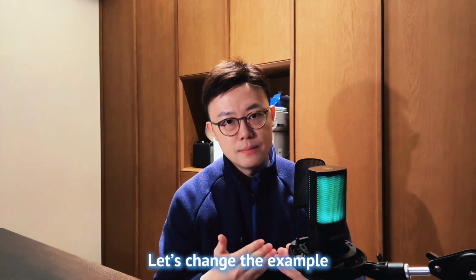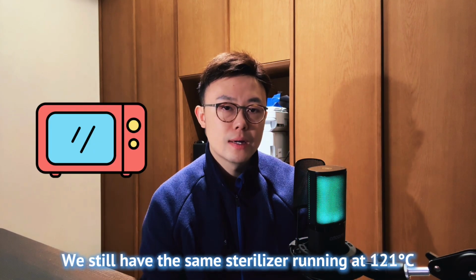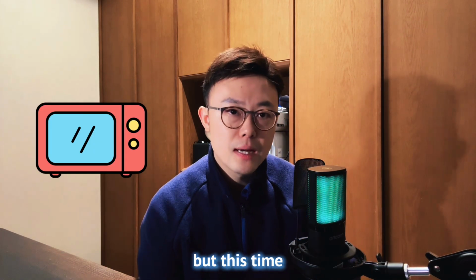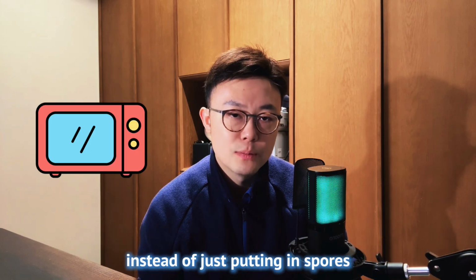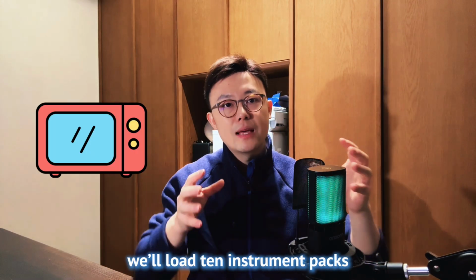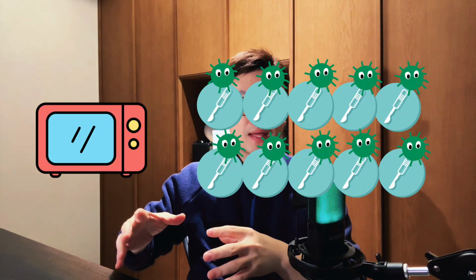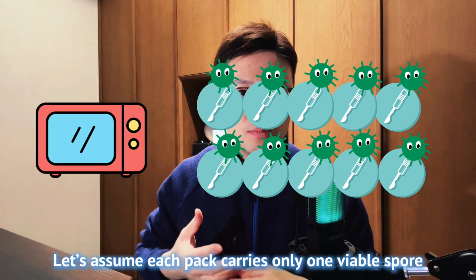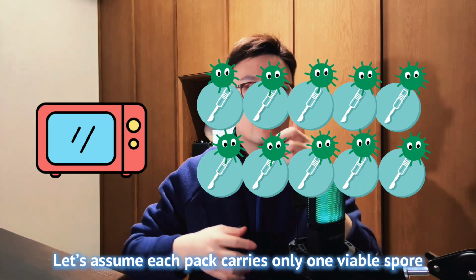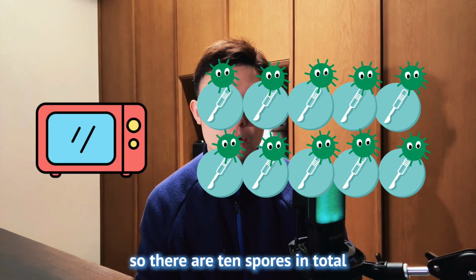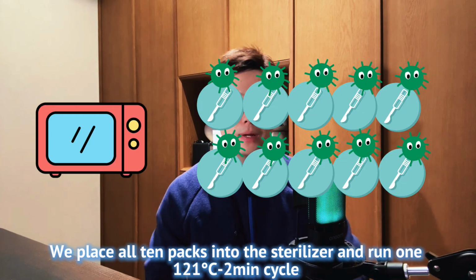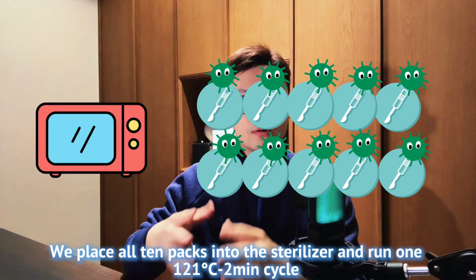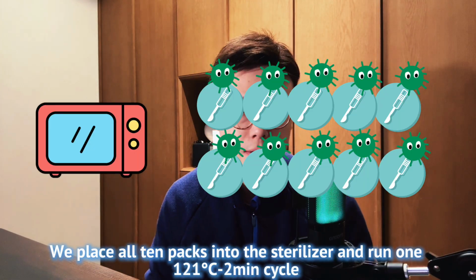Let's change the example. We still have the same sterilizer running at 121 degrees, but this time, instead of just putting in spores, we will load 10 instrument packs inside. Let's assume that each pack carries only one viable spore. So there are 10 spores in total. Place all 10 packs into a sterilizer and run this 121 2-minute cycle.